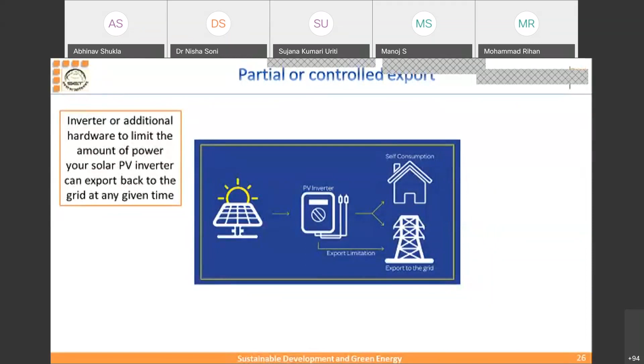For example, if I'm installing a 100 kilowatt plant, I can restrict the export to 50 kilowatt. Even though the plant can export 100 kilowatt, I can restrict it to 75, 70, 60, 40, 10, or 0. It is my choice, done through programming or setting changes in the inverter itself. Inverters are very sophisticated now. This is known as partial or controlled export.